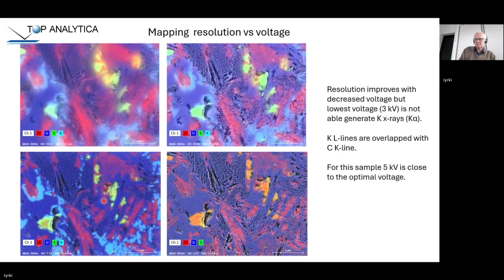This lateral resolution and analysis depth can be calculated or modeled by using Monte Carlo simulations. For example, the electron beam is coming here, and during this simulation the electrons scatter, and following the physical laws, they form a kind of pear-shaped distribution where the electrons are penetrating. And you see that when we reduce the voltage, this volume where the electrons are able to generate X-rays is decreasing. Here the lateral resolution is around 500 nanometers, and if we go down to 1 kV, it is something like 10, 20 nanometers.